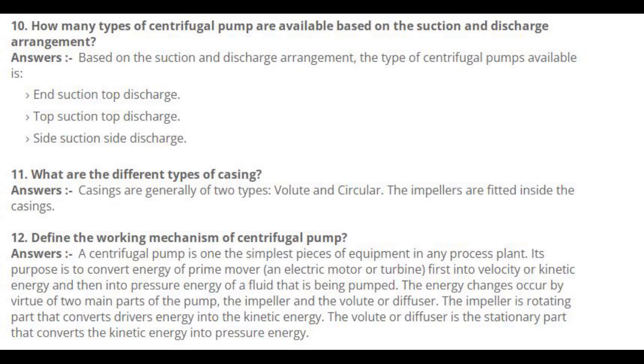Number 12: Define the working mechanism of a centrifugal pump. A centrifugal pump is one of the simplest pieces of equipment in any process plant. Its purpose is to convert energy of a prime mover — an electric motor or turbine — first into velocity or kinetic energy, and then into pressure energy of the fluid being pumped. The energy changes occur by virtue of two main parts: the impeller and the volute or diffuser. The impeller is the rotating part that converts the driver's energy into kinetic energy. The volute or diffuser is the stationary part that converts kinetic energy into pressure energy.